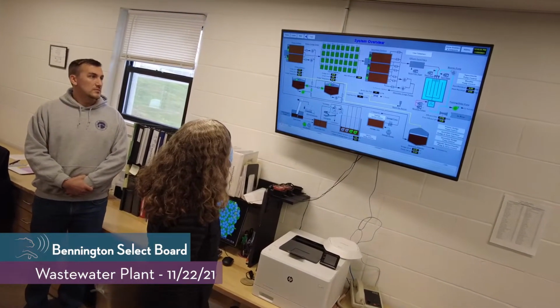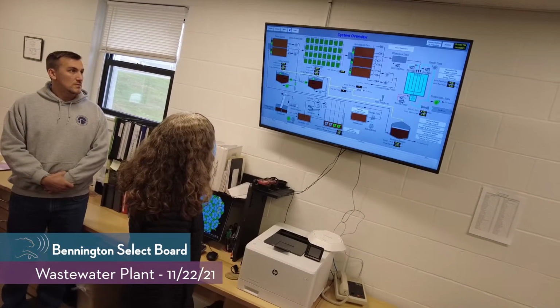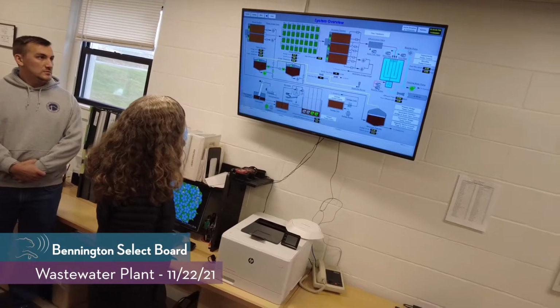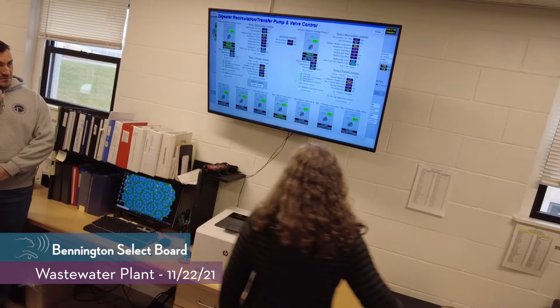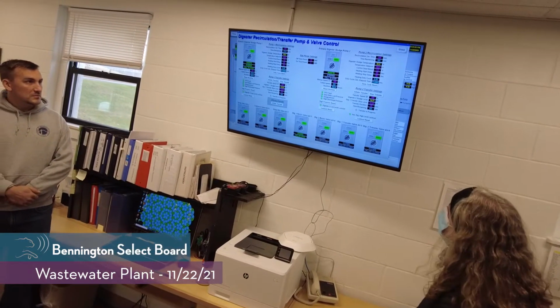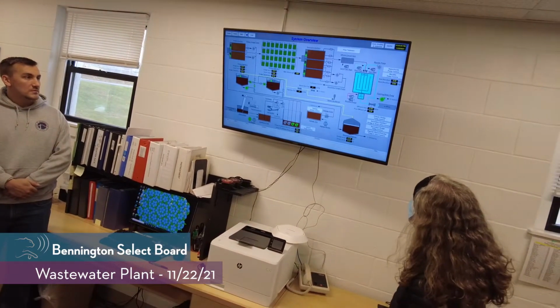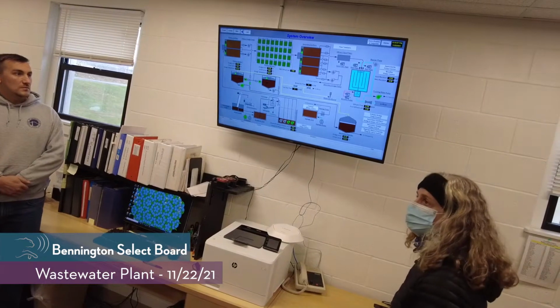There are some adjustments we make here, and you can control quite a bit. We can control certain pumps, times, and processes right through SCADA now. This also controls our alarm set points, so if a tank goes high or low, or chlorine goes high or low, high flows, high wet wells, or a pump fails, we get an alarm for anything in the plant.